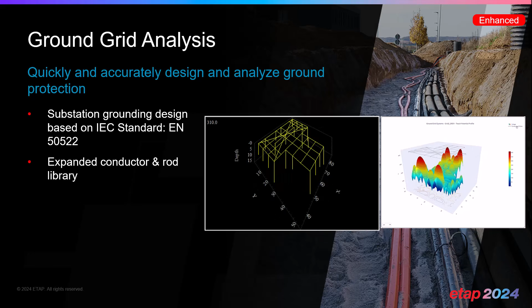Substation ground grid has also been enhanced by having an expanded conductor and rod library. These are the fundamental building blocks for the substation ground grid. And when you're done with the grounding design in terms of rods and conductor placement, you can use the IEEE Green Book method, the finite element method, and now in ETAP 2024, the EN 50522 method for evaluating your ground grid design.